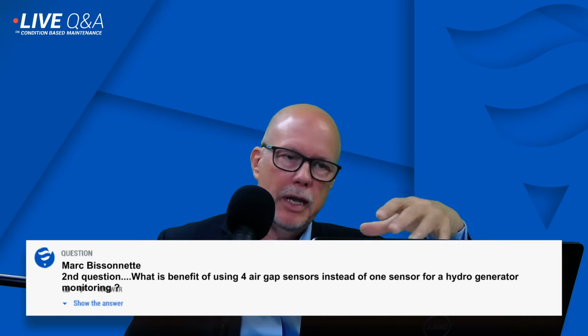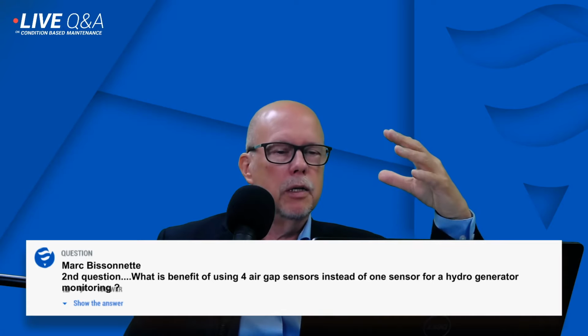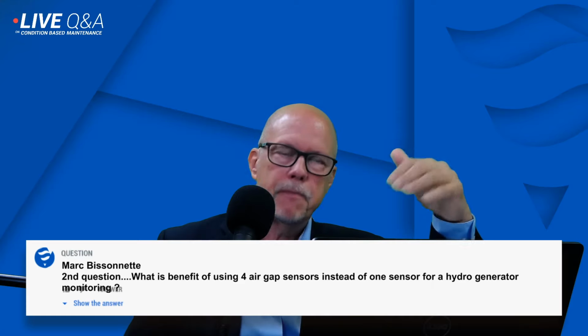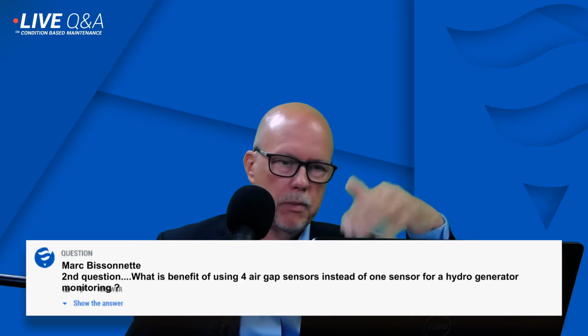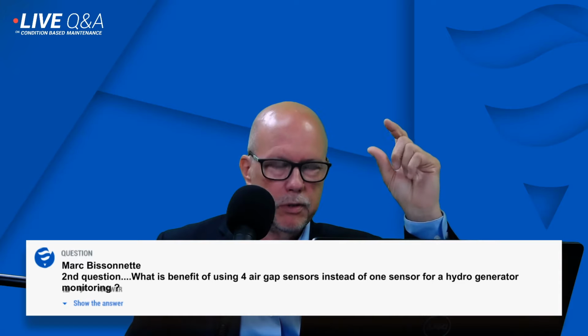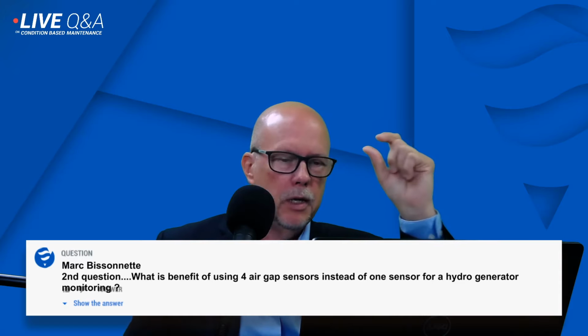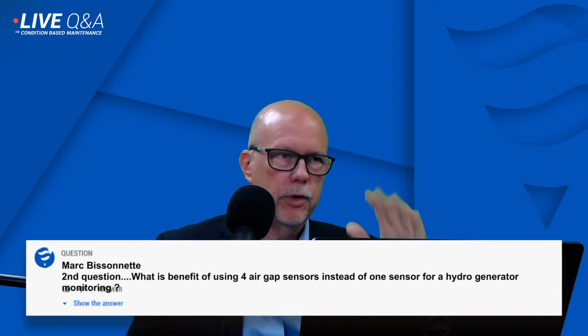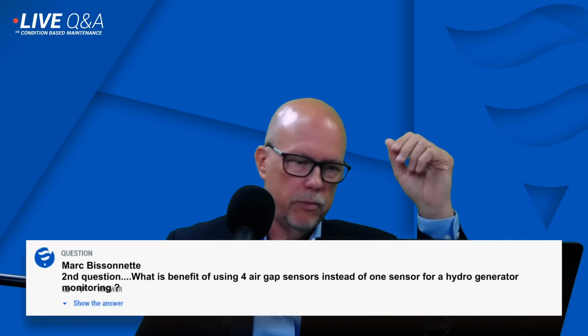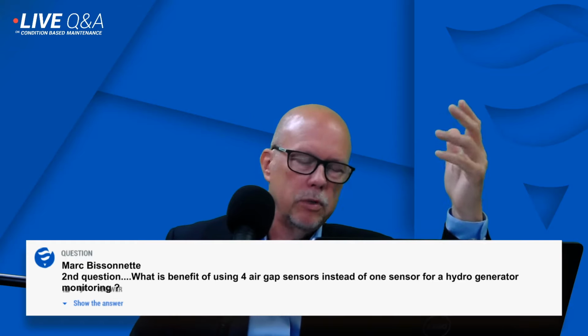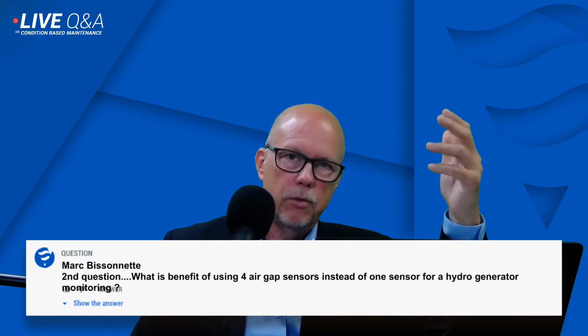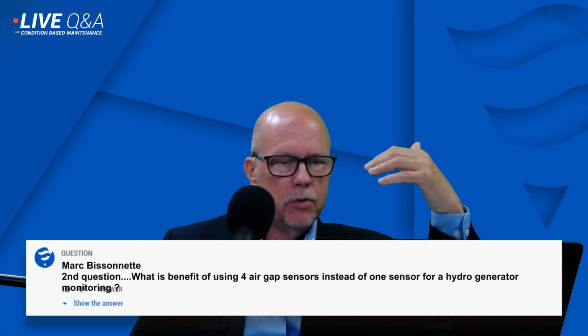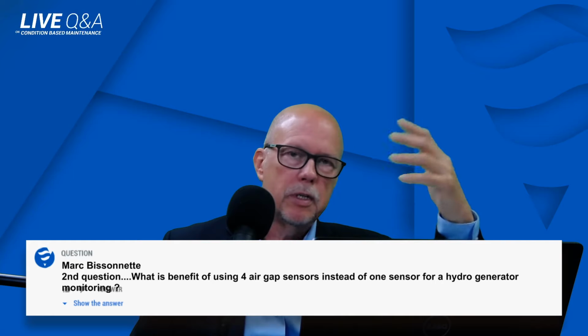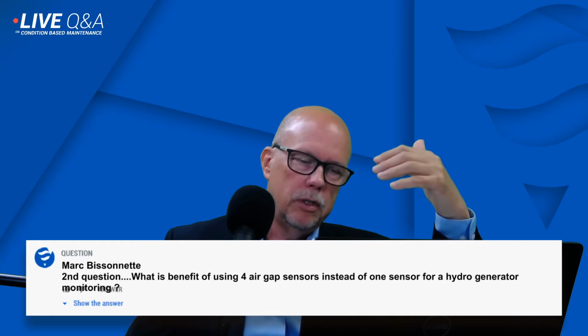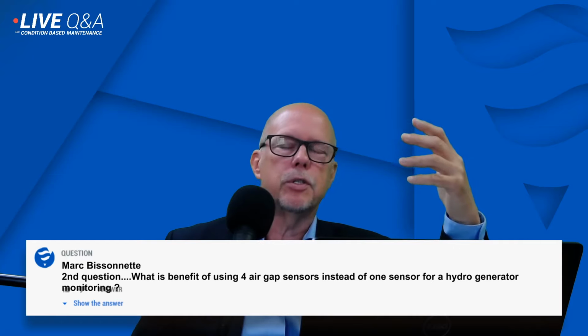We go up to 6, 8, and 12. In some cases, when the stators are very high, we will put sensors on the top and on the bottom. And in some cases, people will put a certain number of sensors at the top, and they'll put just 1 at the bottom for verticality and to look at the rotor shape, which is not a bad idea, but it won't tell you what the stator shape looks like at the bottom. So using 1 sensor will give you information on the rotor, but it's not going to give you information on the stator. So the more information you have, the better position you're in to make assessments.